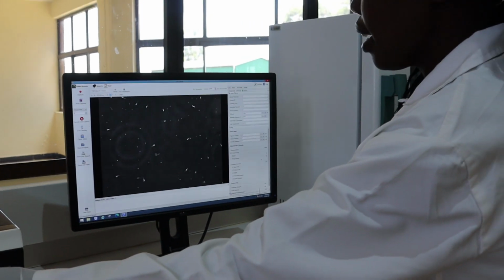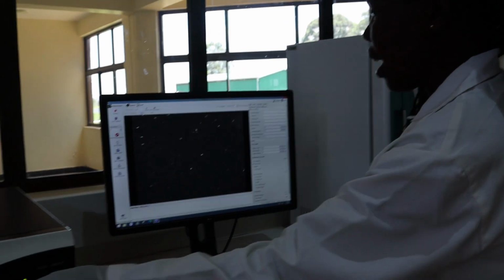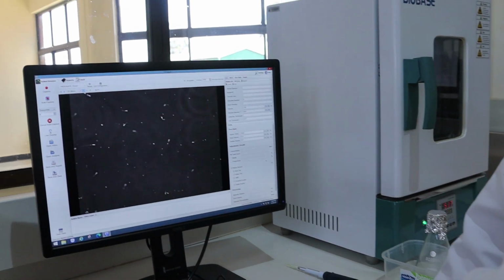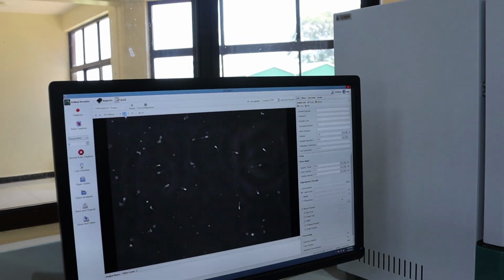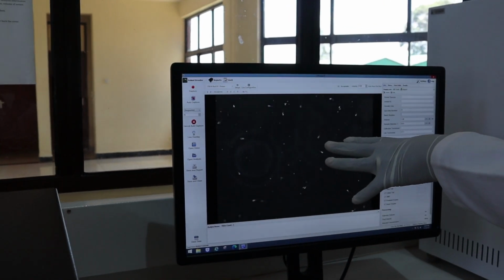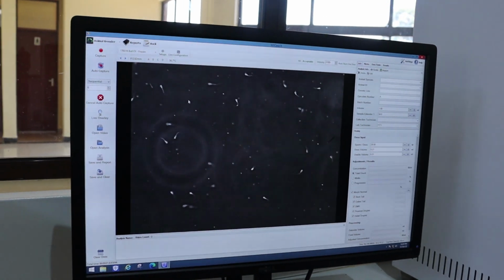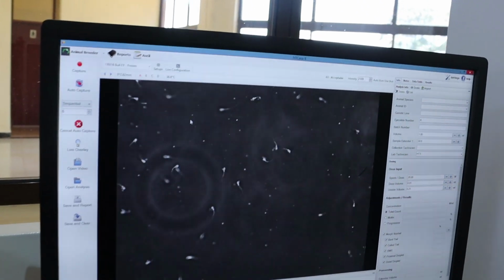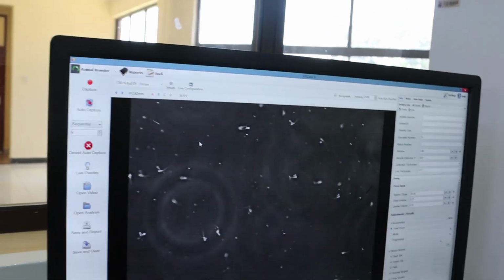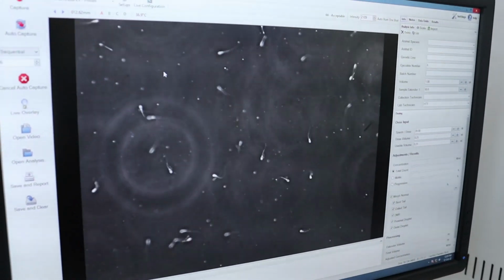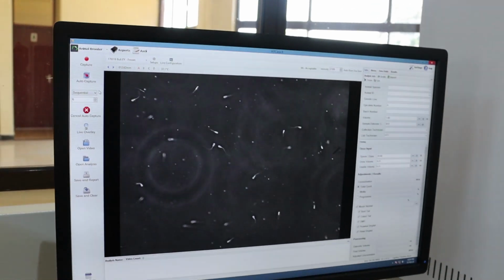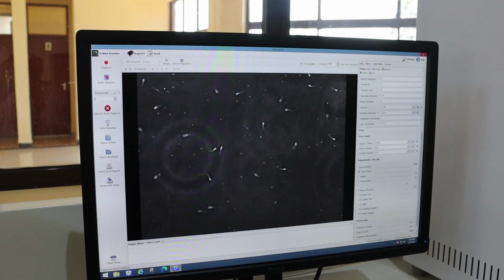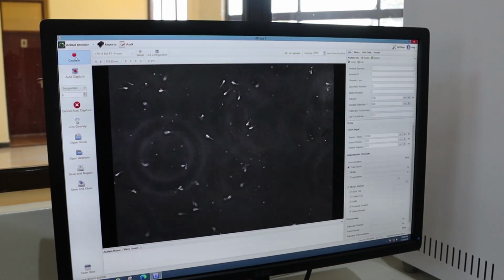So this is diluted semen, in this case, so we have the semen there. So in case I want to see the different fields, I need either to zoom in or zoom out to see the different fields before analysis. Then what I need to ensure again is that the illumination of the machine should be well illuminated. In that case, it should be at 65%. And the temperature of the machine should be at 37 degrees. So from there, I need to capture at least 6 fields for the machine to analyze the semen well. So I'll capture 6 of them.